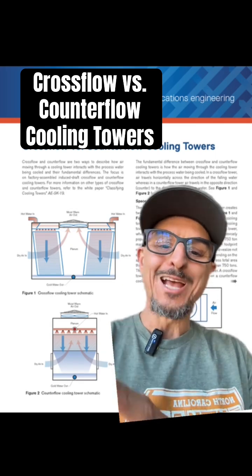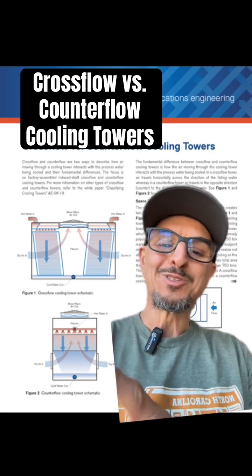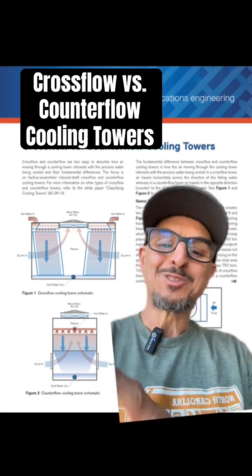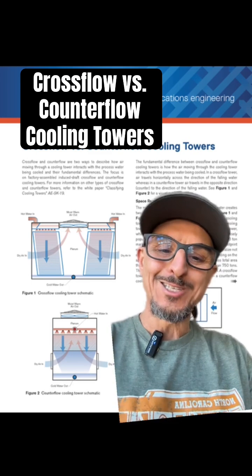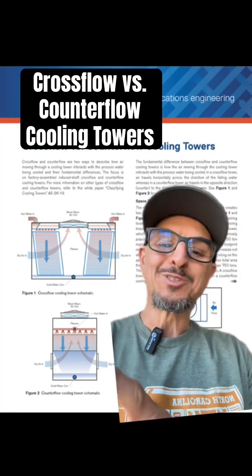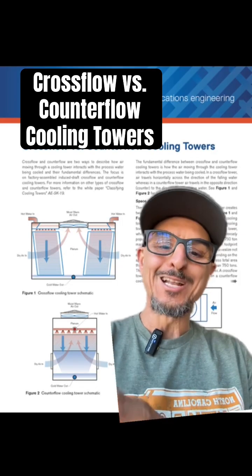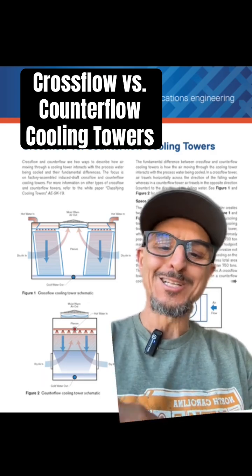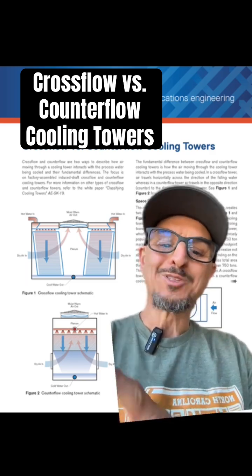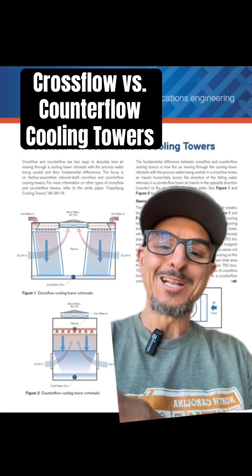Another difference is the way the water is fed and flows through the fill. In a cross flow application, the water is fed to a basin and the nozzles gravity feed the water through the fill. In the counter flow, the condenser water is fed through a piping distribution and the pressurized water is pushed through the nozzles and sprayed over the fill, so you have a little more pump work on the counter flow. To summarize, if you've got a tower under 750 tons and real estate is a premium, start looking at the counter flow tower.